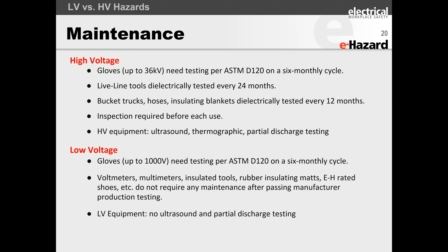And for high voltage equipment, we look at ultrasound, we look at thermographic testing like infrared temperature testing, as well as partial discharge. Partial discharge is to be able to pick up that corona and that arcing. Low voltage, on the other hand: voltmeters, multimeters, insulated tools, rubber insulating mats, EH-rated shoes, etc. Folks, after you buy those things, they don't need any inspection. I mean, any maintenance or testing on them, right? There's no rules for it. They tell you you can have a cursory glance over it, but there's no electrical stress testing as you get in high voltage. All right. So maintenance even has different requirements for high voltage and low voltage.